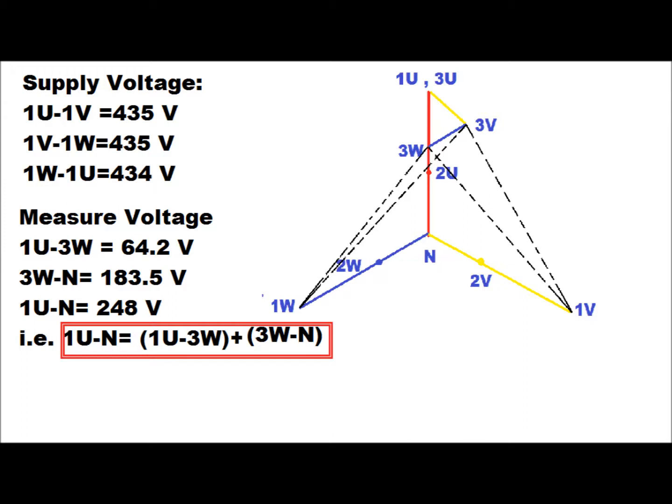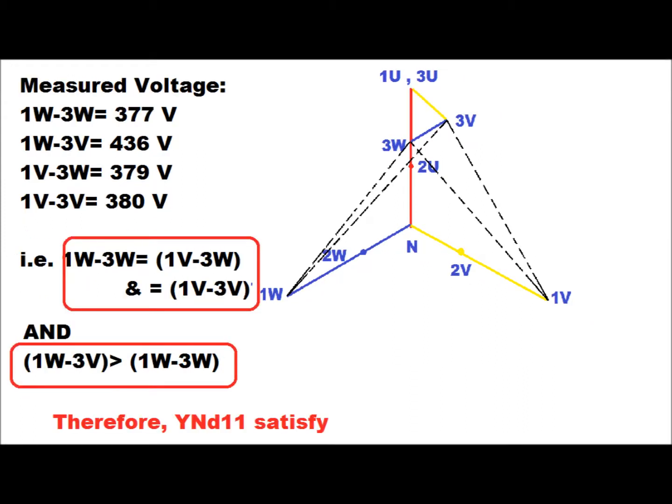We measure the voltage between 1U and 3W, which comes to 64.2 V; between 3W and N, which comes to 183.5 V; and between 1U and N, which comes to 248 V. The measured voltage between 1U and N — that is between red phase and neutral of primary winding — is equal to 1U-to-3W plus 3W-to-N.